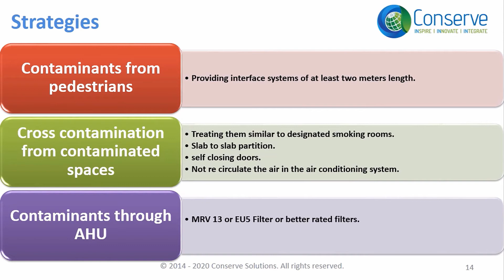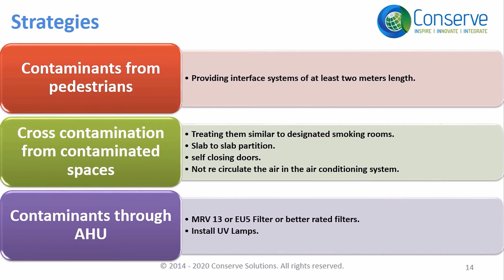Contaminants from FAHUs or AHUs can be addressed by first strategy, providing MERV 13 or EU 5 or better rated filters in FAHUs or AHUs. We will discuss about MERV and EU in the next slide. The second strategy is to install UV lamps in FAHUs or AHUs, which will disinfect by killing bacteria and germs.